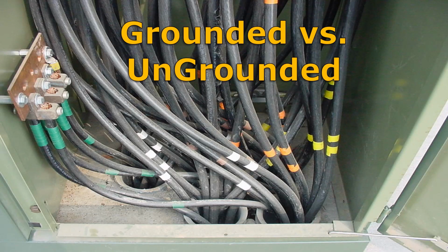Grounded versus ungrounded. In the 2002 edition of IEEE 1584, when the arc flash tests were established, the first fraction of a cycle or so was really erratic. Then we'd hit more the stable part of the arc. And so what was happening, the equations reflected a difference in incident energy between whether the system was grounded or ungrounded. Let me explain why that was, and then what was done to address it in the next edition.